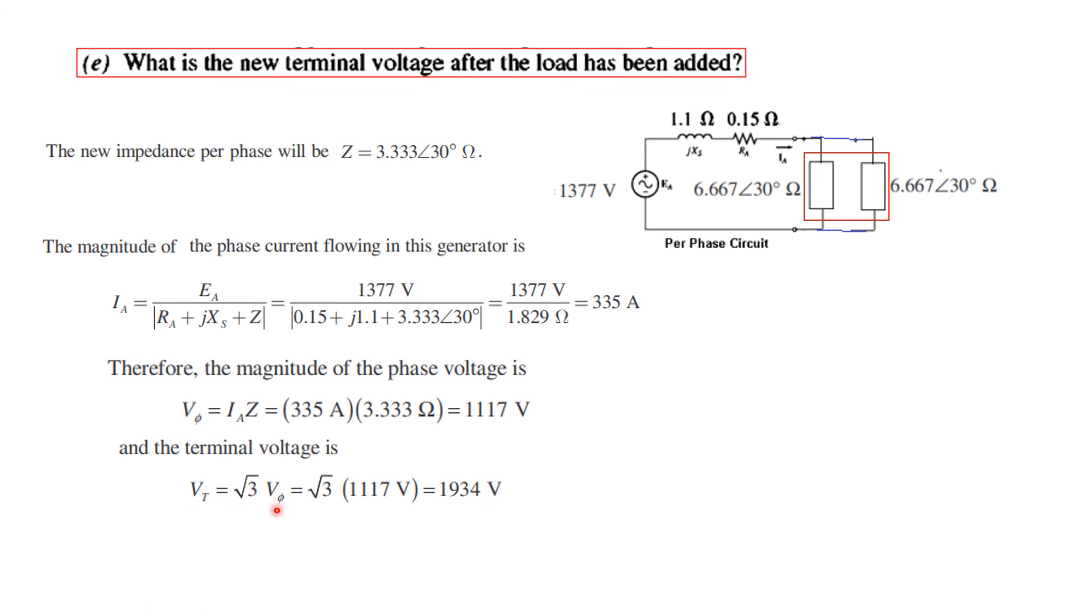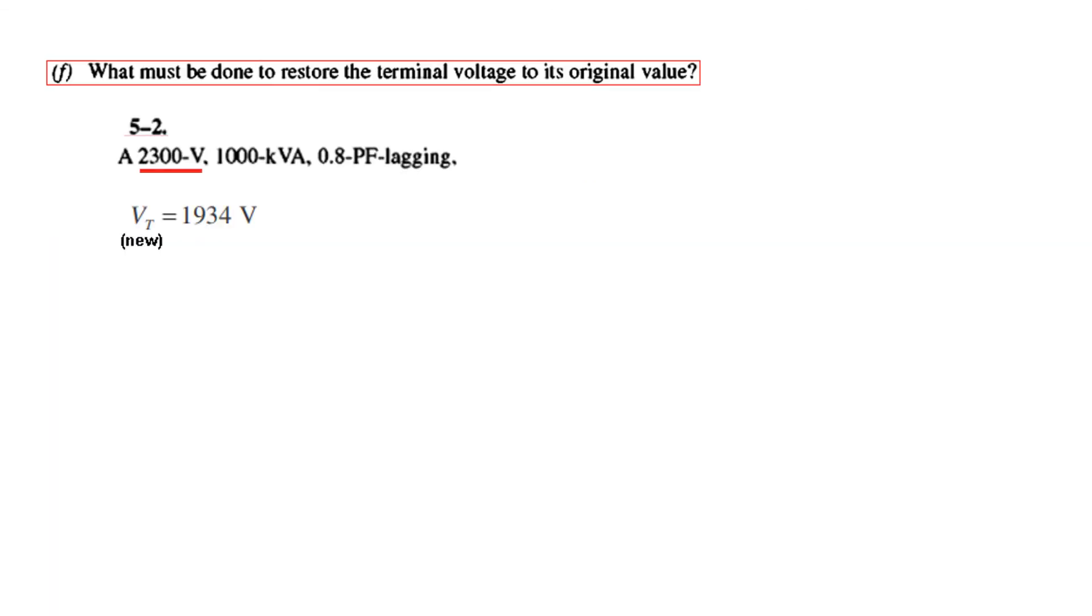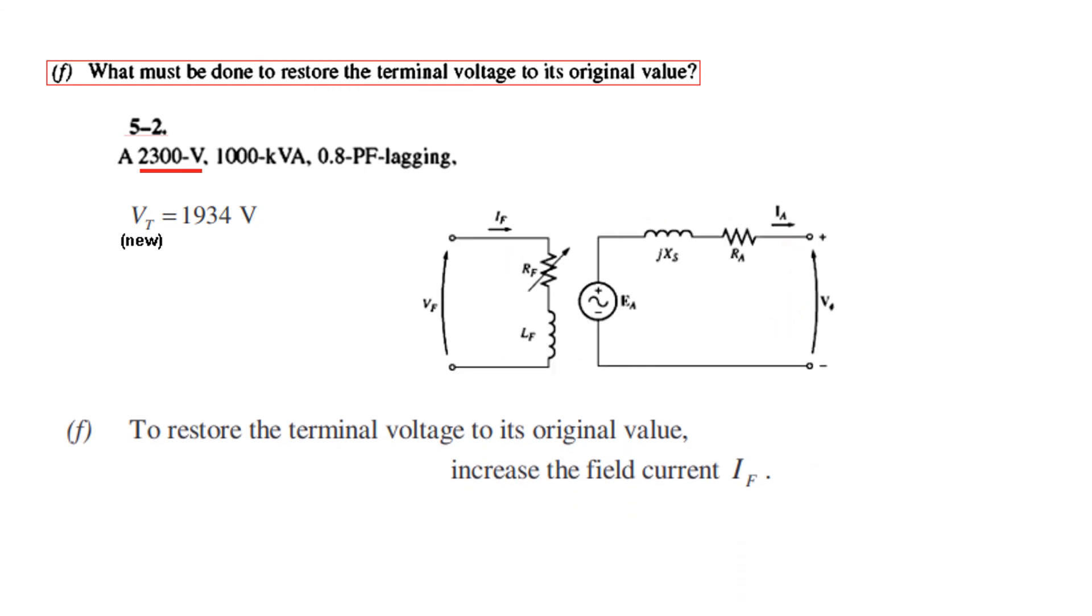Part (f): What must be done to restore the terminal voltage to its original value? The original terminal voltage was 2300 volts. To restore it, we need to increase the field current by varying the resistance, or by increasing Vf. Thank you for following this question.